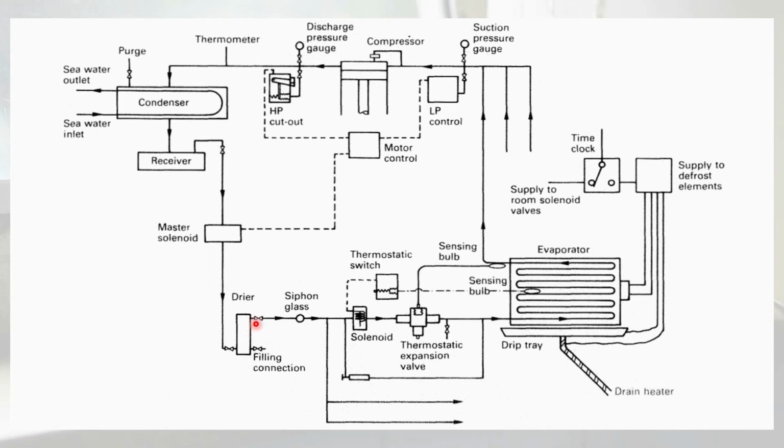Here the question may arise, what happens if water enters the refrigerant? If water enters the refrigerant, there is a pressure drop that happens in the thermostatic expansion valve. Due to the pressure drop, the water may get stuck in this thermostatic expansion valve and freeze up. So the flow of refrigerant from the TXV to the evaporator may be stopped completely. This I will explain in further videos in a better way. Now let us focus on the actual system.